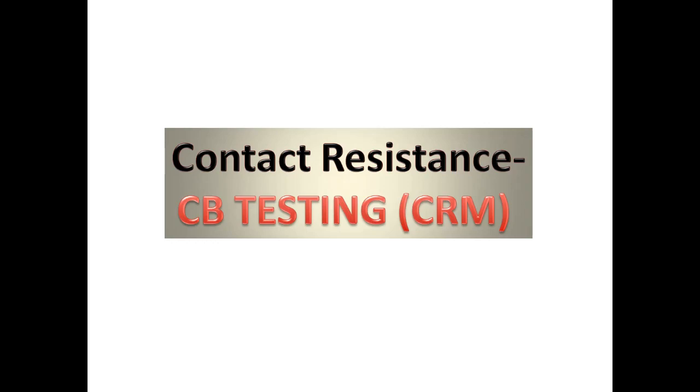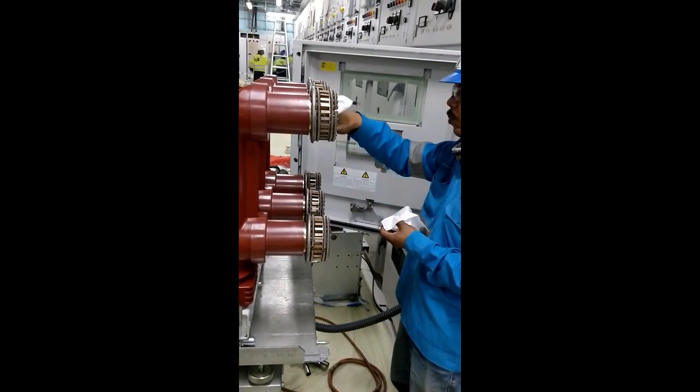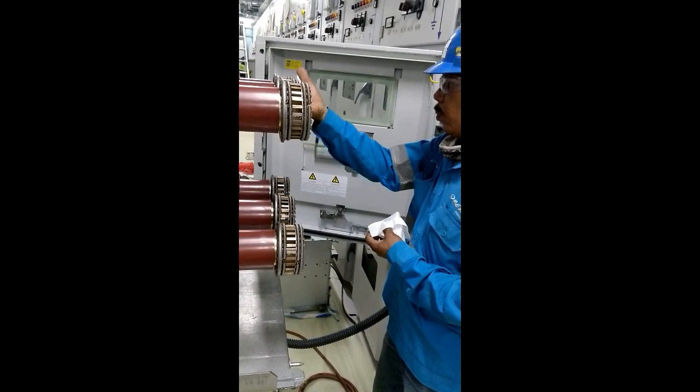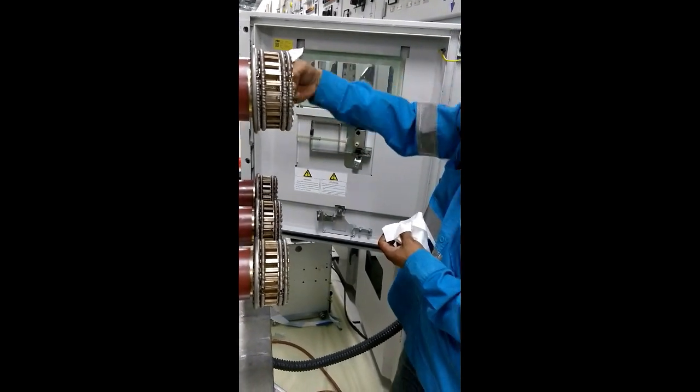First we have to rack out the CB from the module and we have to clean the contact with white cotton.